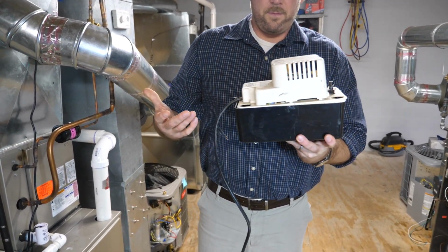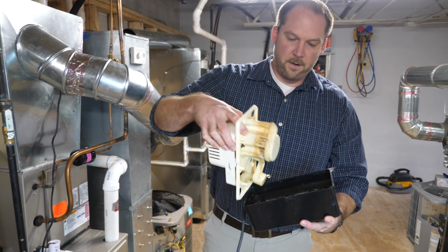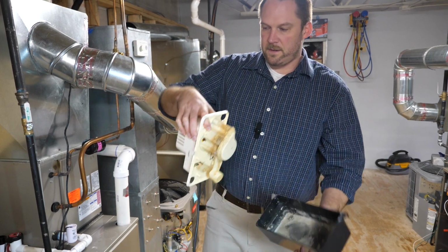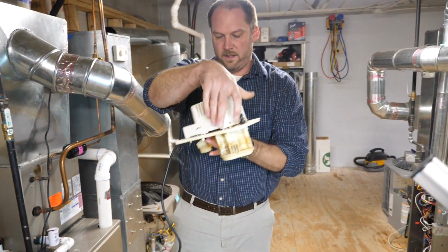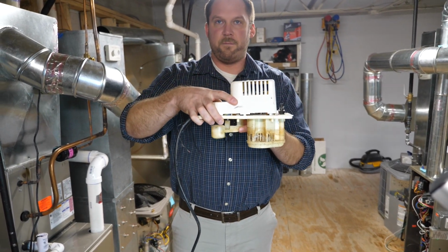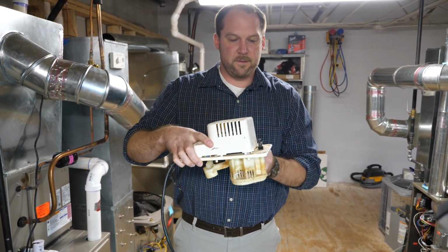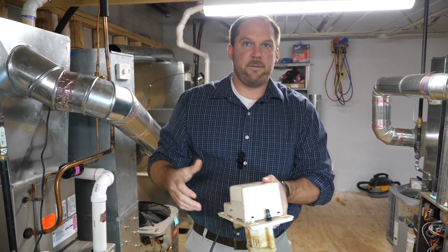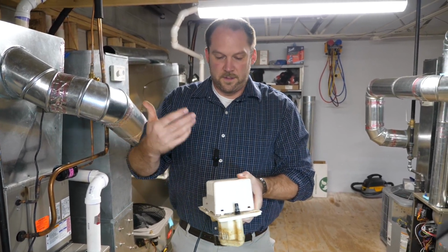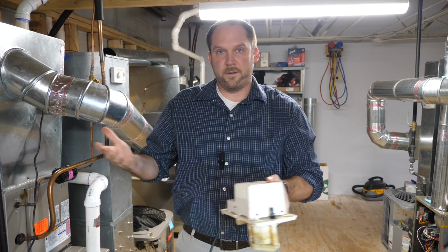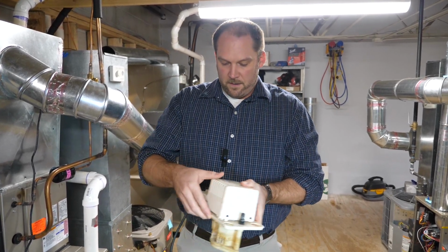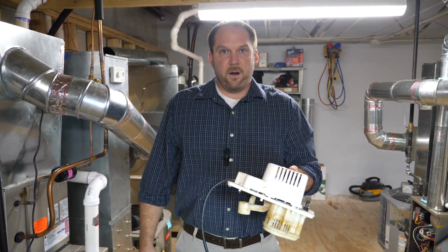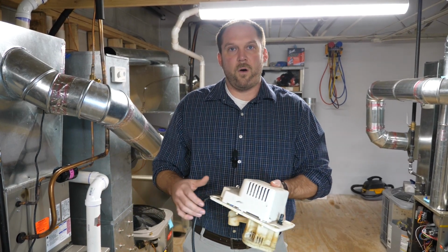This is what a condensate pump looks like. Common issues are the inside of it just gets really, really dirty, like kind of like this one, where it just messes up this float mechanism. It gets a lot of debris in there. It messes that float up to where it doesn't turn the pump on to discharge out here. And if there's a blockage in here, the water is not going to have anywhere to go. So it just kind of overflows that reservoir and just leaks all over the place. There are safeties now on them that you can rig them up to where they automatically turn off the unit to where it doesn't produce any more water.